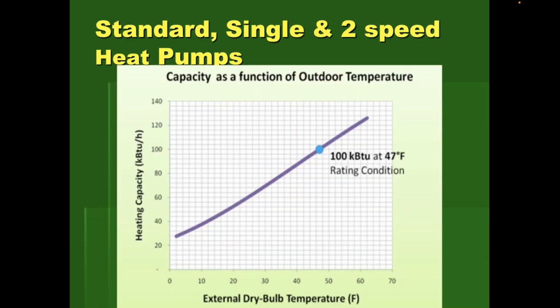Now, another thing that's important to recognize is that the capacity is a function of outdoor air temperature. If you look at a traditional single or 2-speed heat pump, let's say we start out at 50 degrees, we might have 100% of the capacity of our system. Let's say we had a 4-ton system, and it'd be operating at 4 tons at 50 degrees. But look how quickly the curve drops off as the outdoor temperature approaches 0. We might have 22% of our capacity at 0 degrees, whereas at 50 degrees we had 100% of our capacity.